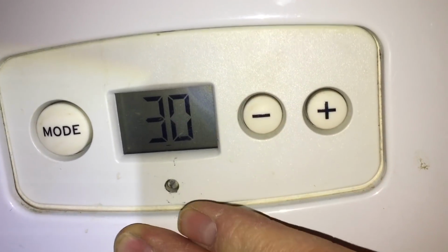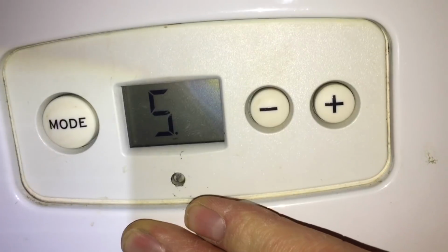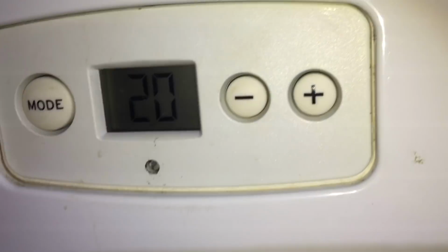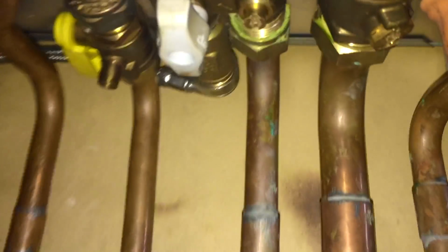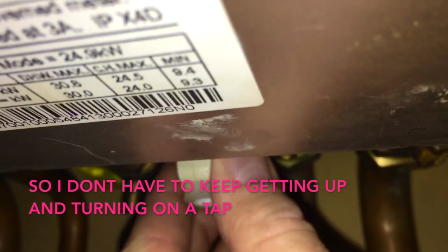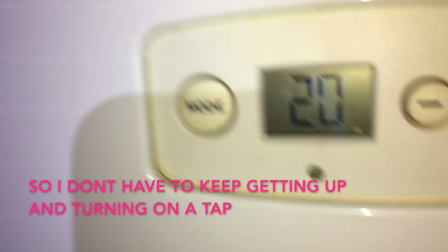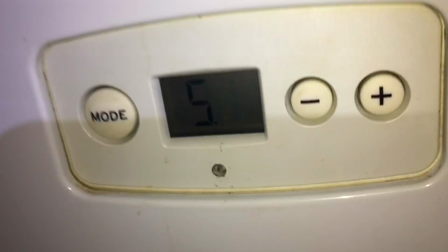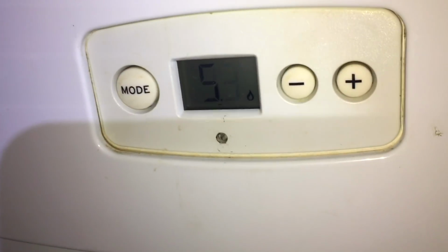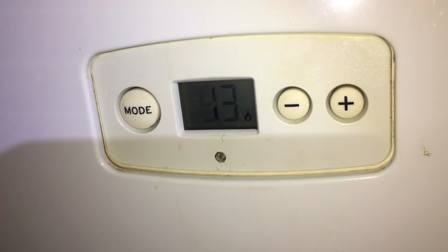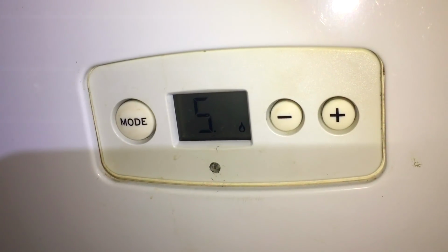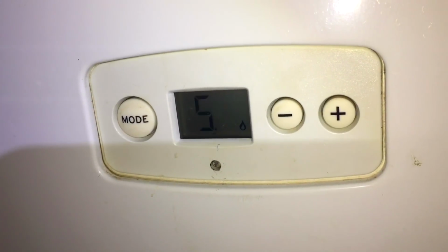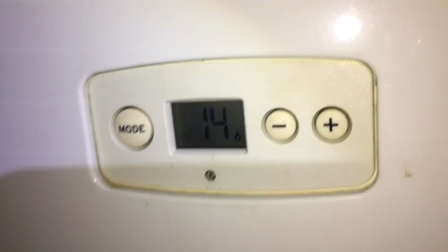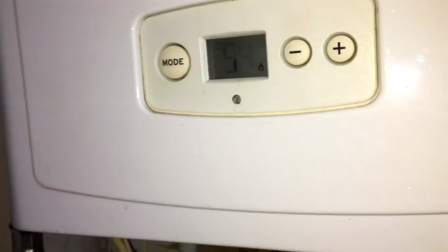And the way I do this, so it's S30, S20, they're normal operating S codes. I've got a hot tap open in the bathroom already, and what I've done with this boiler is I've used a filling loop, because if you use the filling loop on a Vaillant or Glowworm, it turns the hot water on and off as well. So I used the filling loop to turn the water on and off. It takes some time here, but it will lock out.